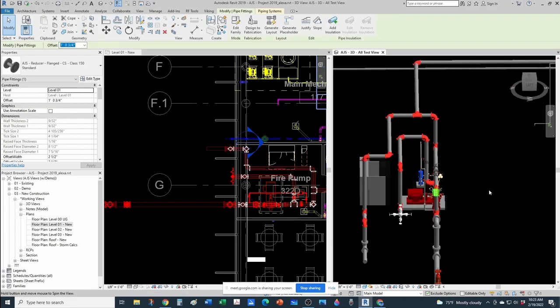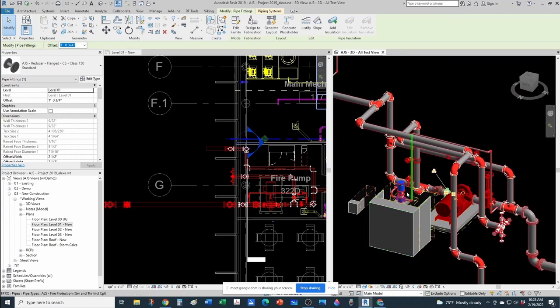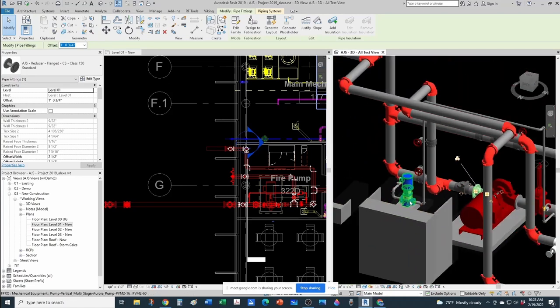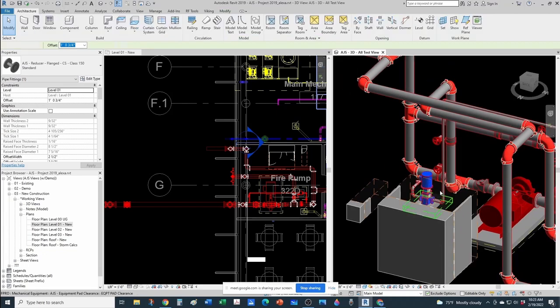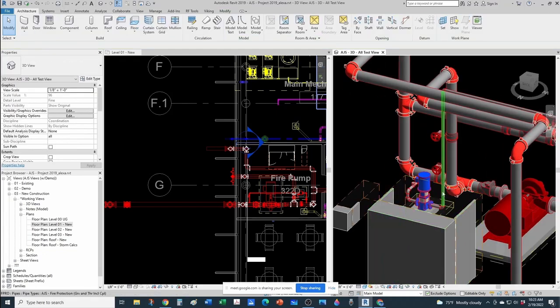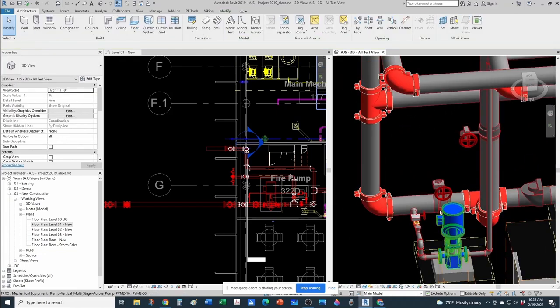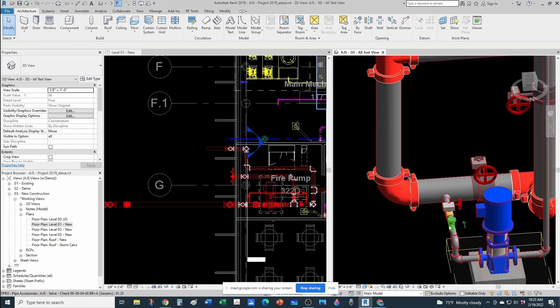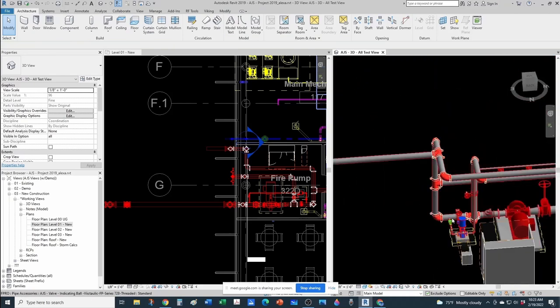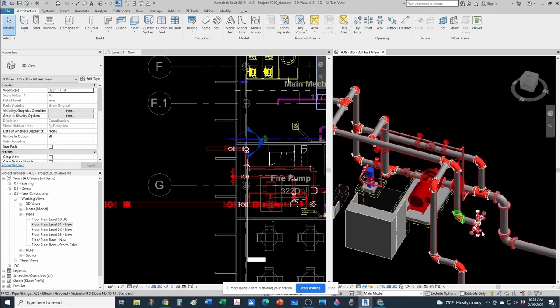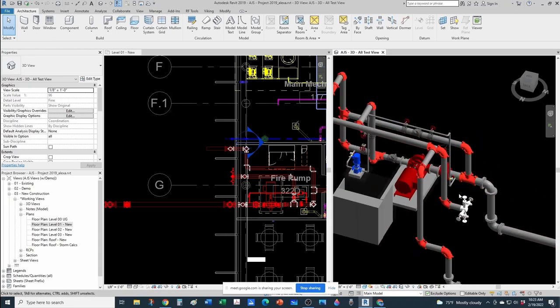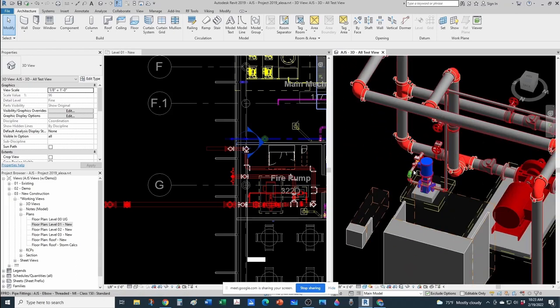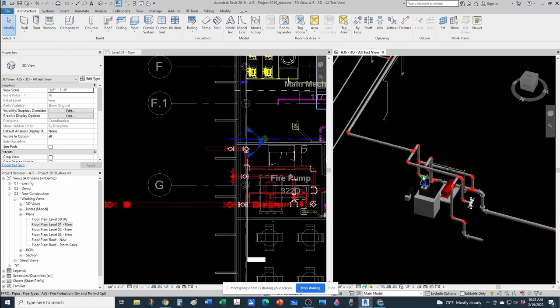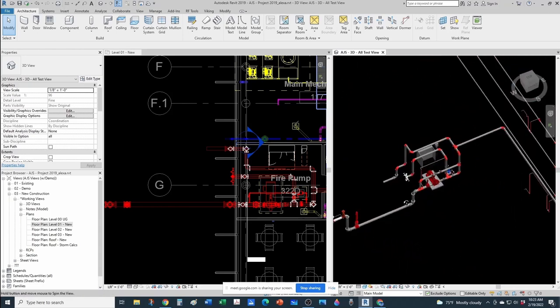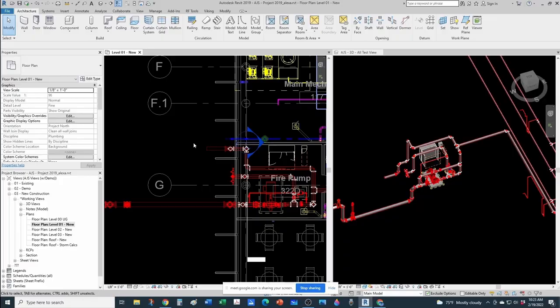And then in addition to that, you have your jockey pump right here. Your jockey pump has to be provided with a suction isolation valve and with a discharge isolation valve and check valve. And then you connect your suction to your suction line and your discharge to your discharge line. Okay, so let's go ahead and try to replicate this.